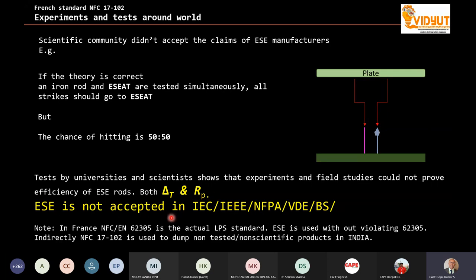As a result, ESE is not accepted in any of the recognized international standards such as IEC, IEEE, NFPA, VDE, BS, or whatever. Even in France, the actual French standard is 62305. In France, the NF C EN 62305 is the actual LPS standard. ESE is used without violating 62305. So if you look at the previous picture, ESE is used without violating 62305 in the sense that they use the word coexist.